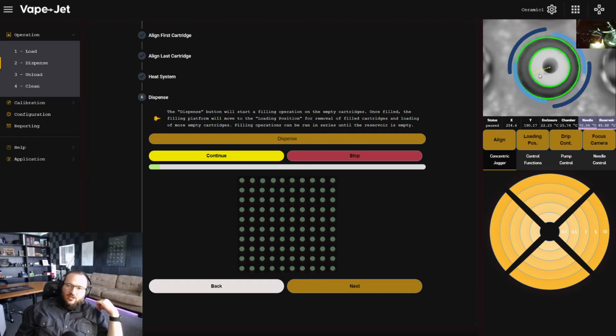This yellow line indicates to the system where it's going to attempt to place the needle. For cartridges with bent center posts, if you inserted the needle at the same place every time, it would scrape the inside of the center post. However, our system measures, detects, and averages this angle, telling the system to insert the needle at the widest point of the cartridge.